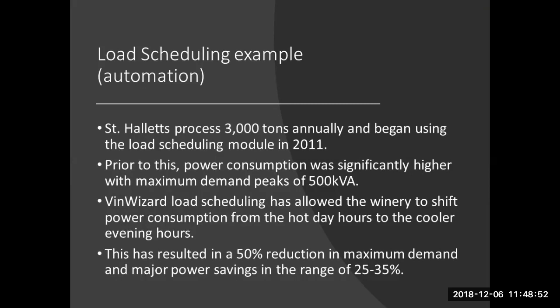Not only were demand savings made, they also resulted in energy savings, because the fridge system was running in off-peak, and because the fridge plant was running more efficiently as well, they had energy savings in the range of 25 to 35% as well. So heaps of opportunity to shift your refrigeration to nighttime. Now, again, this was an example of using an automated system, but you can do it manually as well.